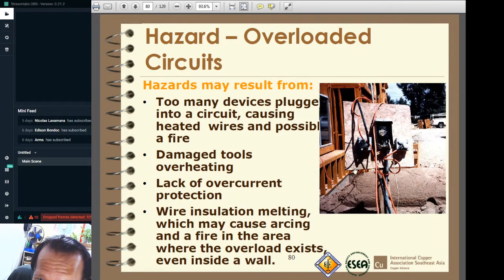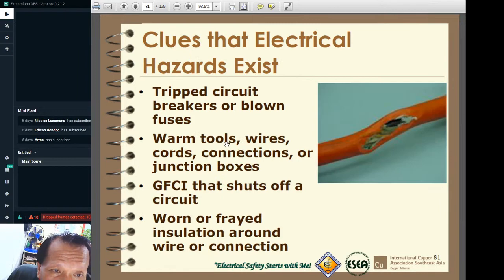Hazards may also result from this kind of installation. It looks like a temporary wire installation, but it is too dangerous. Again, like I mentioned, old wires must be inspected, and if it is possible to cover them with electrical tape, we must do so, so that they may not be exposed to moisture or water or to people.